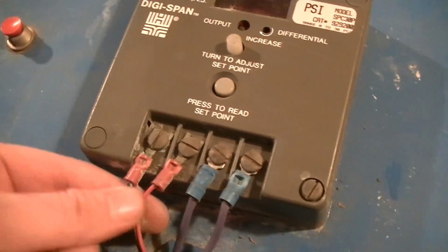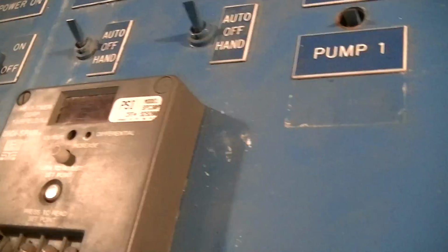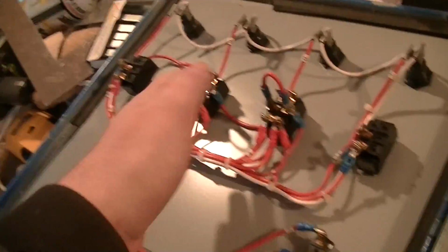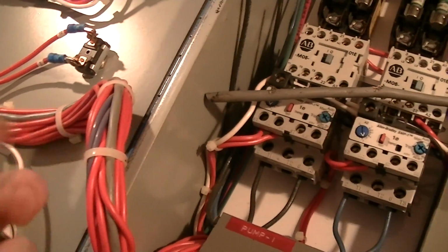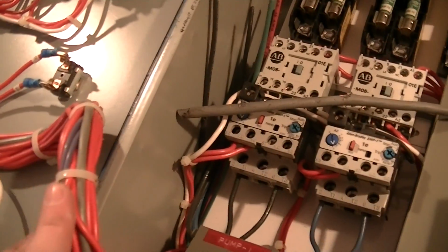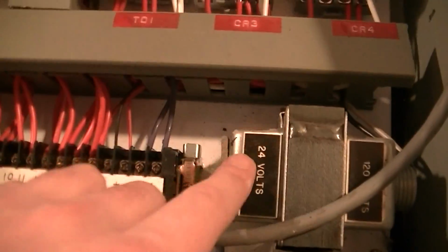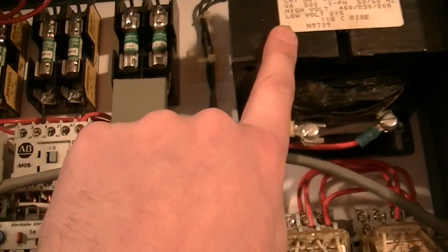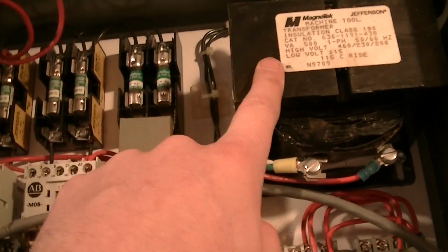And of course, the thin wires are just for the transducer that this reads. There's the switches, quick default. And inside, you got the back side of the switches and all the idiot lights, just wires, blah blah. Fairly standard wiring loom. 2 purple wires being the 24 volts, most likely a different color just because they're a different operating potential. There's the 24 volt transformer for running the relay, as well as a 500 volt ampere control transformer for running everything else.